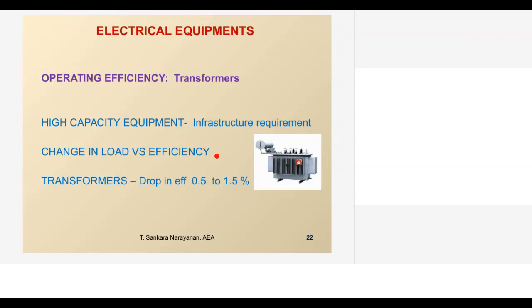Change in load versus efficiency. For most industrial transformers, we can get this specific information from the transformer test certificate. Otherwise, in general, the drop in efficiency in a transformer is just 0.5 to 1.5%. This will change depending upon the individual manufacturer and the rating of the transformer. So if the design efficiency is higher, the drop in operating efficiency is less.